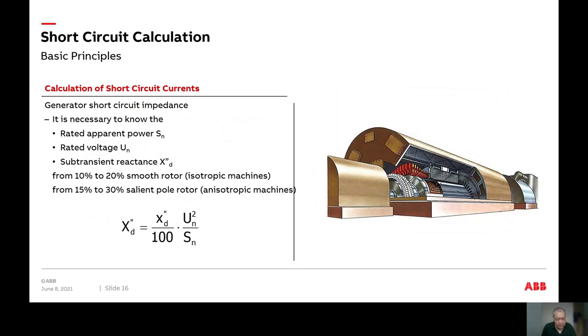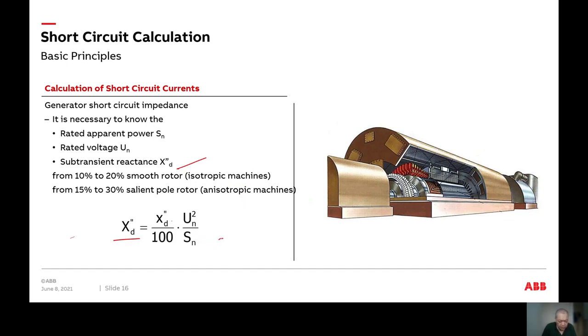Generators are also able to provide current — they are another source. We can find the impedance of the generator based on the sub-transient reactance, Xd double prime. We can either find the impedance first then calculate the current, or jump straight to finding the current using the sub-transient reactance directly.